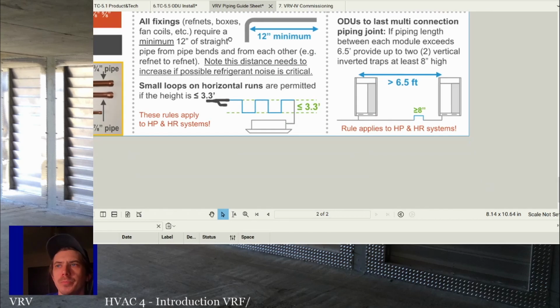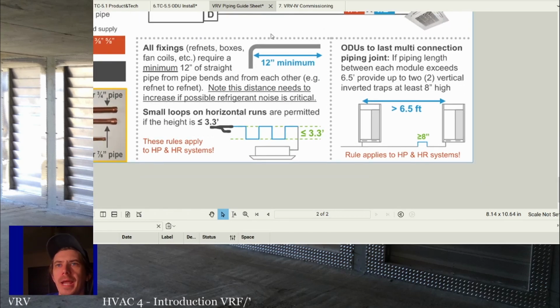12 inches minimum of straight pipe between anything: any fitting, refnet, boxes, fan coils, 90s, whatever. 12 inches of straight pipe. If you need to make two changes in direction, 24 inches of straight pipe between them is what you want to do. Minimum 12. Try and remember it as 24.